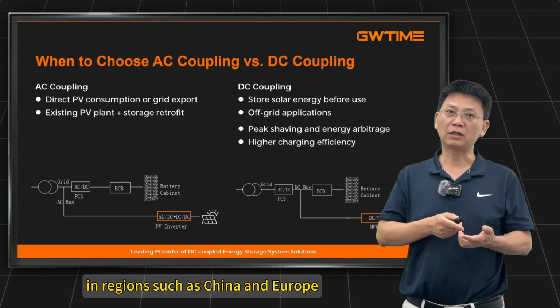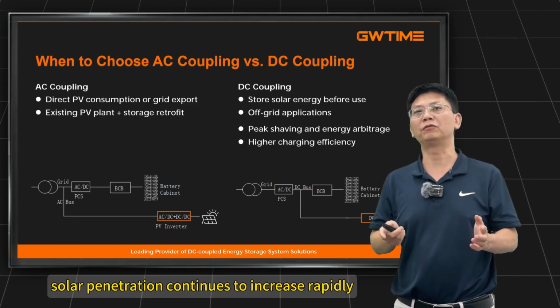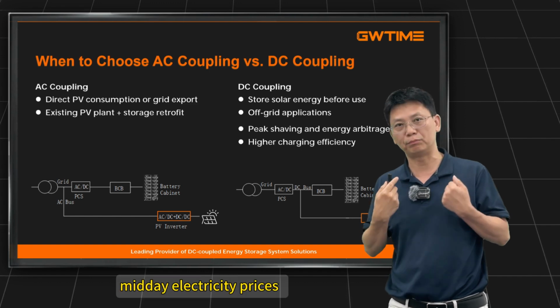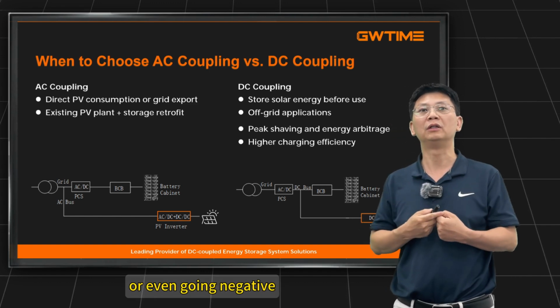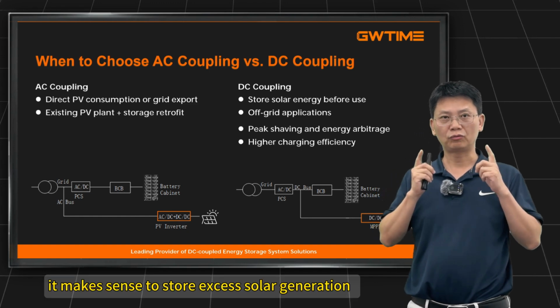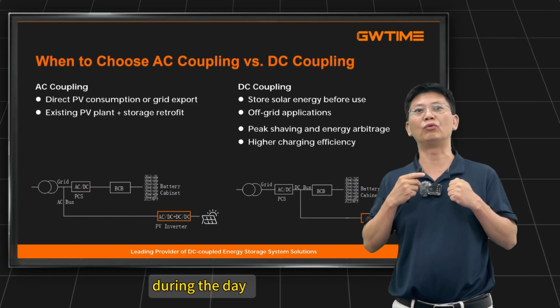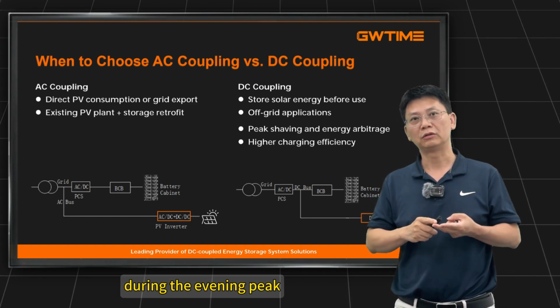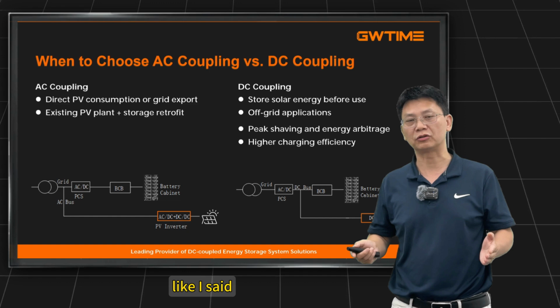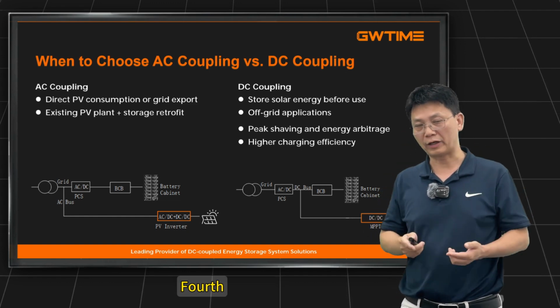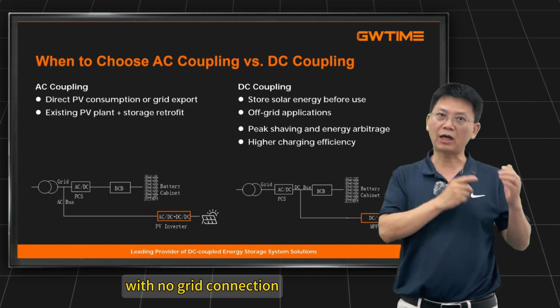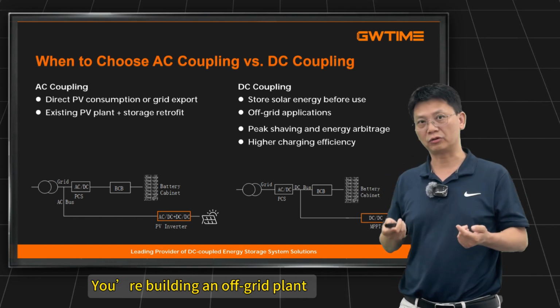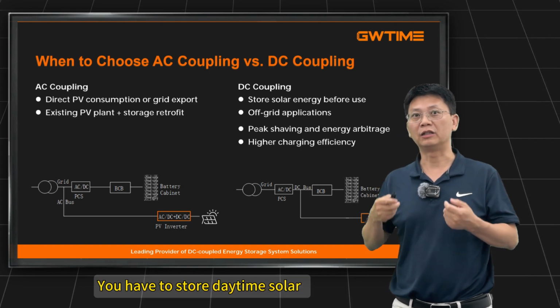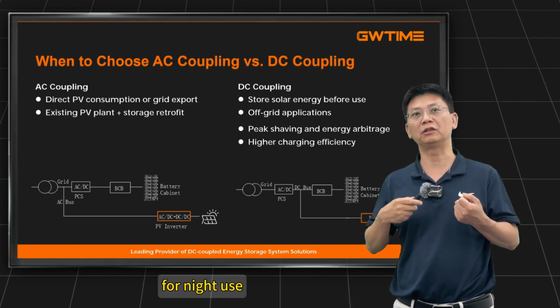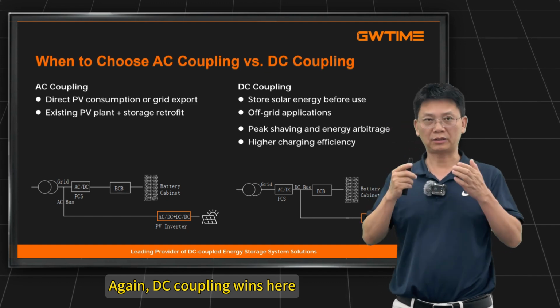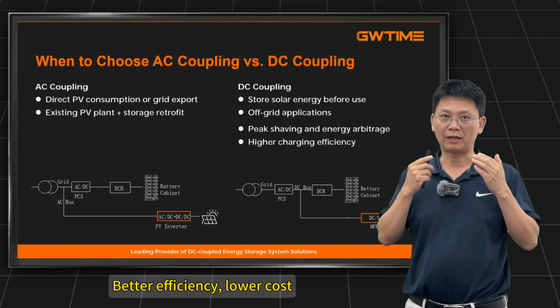Third, in regions such as China and Europe, solar penetration continues to increase rapidly. As a result, midday electricity prices are hitting zero or even going negative. In this scenario, it makes sense to store excess solar generation during the day and use it later during the evening peak. That's where DC coupling shines, like I said, higher charging efficiency. Fourth, consider remote areas with no grid connection. You're building an off-grid plant to provide 24/7 power. You have to store daytime solar for night use. Again, DC coupling wins here. Better efficiency, lower cost. No-brainer.